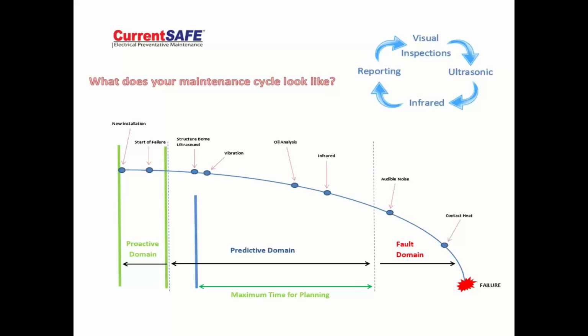Next is vibration. Vibration really only happens with rotating machines and equipment, or fluid flow — you can detect vibration with fluid flow as well. Next is oil analysis, and then infrared. Not everything in an electrical distribution system is insulated with oil, so really we have two things in this predictive domain to use and utilize for our benefit, to help extend the life and condition of our customers' distribution systems to the maximum we can.